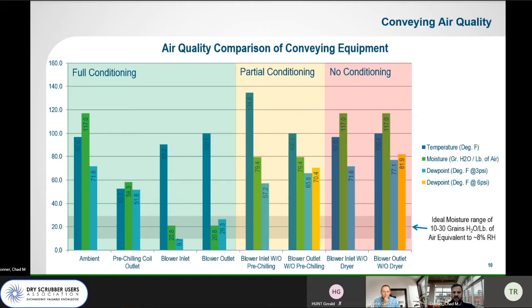If you look at the dew points and moisture for partial conditioning, they are not significantly lower than no conditioning at all, because when the air is not at saturation, the desiccant wheel is not very effective at removing that moisture. From a dew point standpoint, you're still looking at about a 60-degree dew point with partial conditioning versus a 70-degree dew point with no conditioning at all.